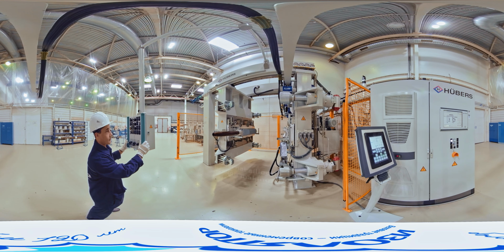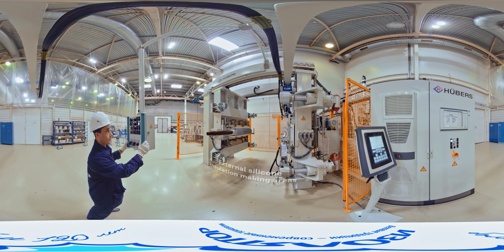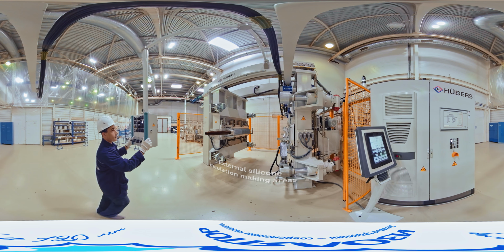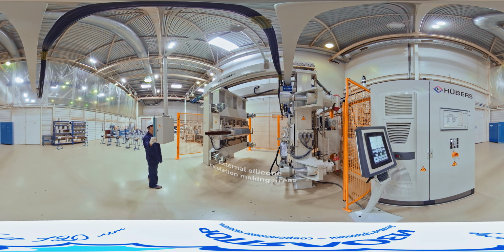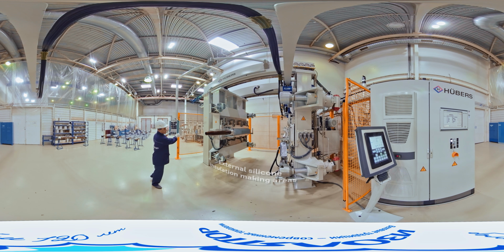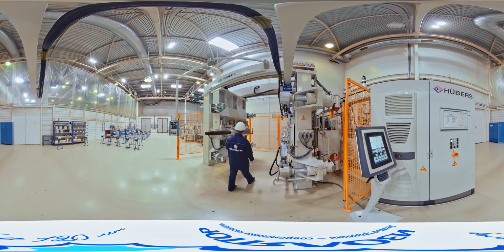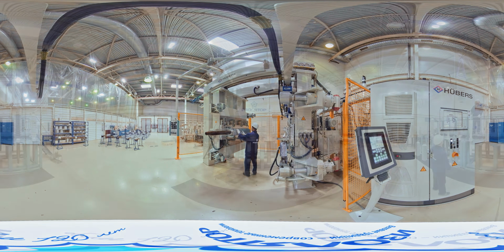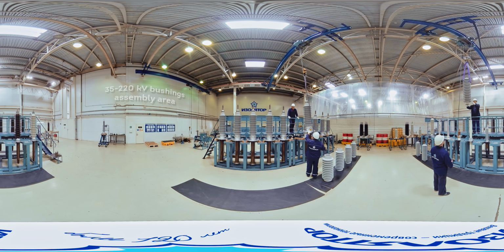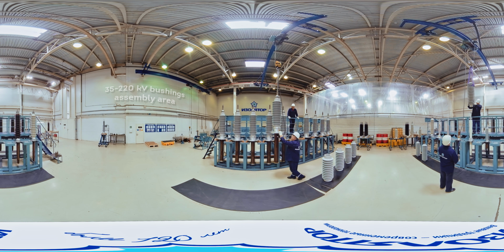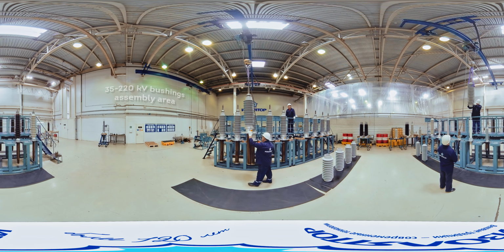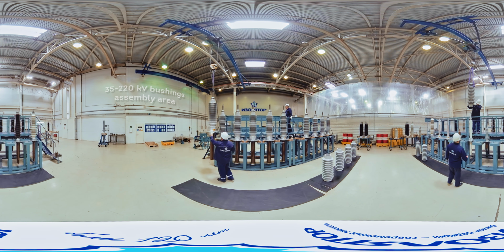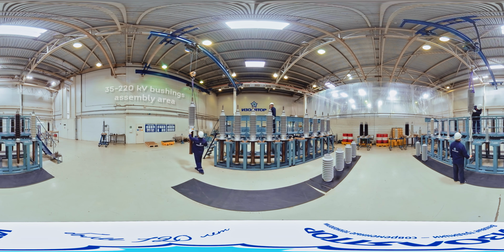of the Izolyator plant. The manufacturing of external silicone insulation is direct casting of silicone rubber onto solid insulation. Full automation of the process guarantees high quality of the manufactured insulation, which does not require additional processing, and a significant reduction in production cycles. The prepared internal and external insulation of the bushing is sent to the assembly shop, where a coupler is fixed on it. Next, external insulation is installed.